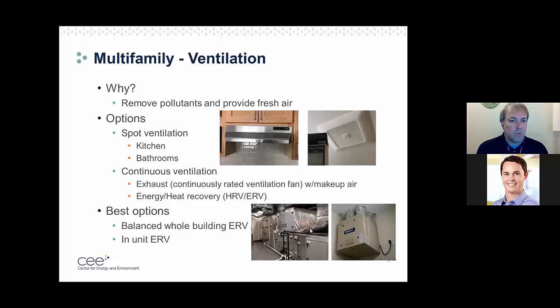Next best option would be in-unit ERVs. They make really tiny ones now, maybe 1.5 feet, 18 inches, 20 inches by cube - really small, you can tuck them into mechanical closets pretty easily. They even have some smaller ones about 8 inches thick by like 20 by 20 or so. They've come out with some really good options now, ones that will serve our Minnesota climate, so you really want one rated to go below 0 degrees for that temperature setting.